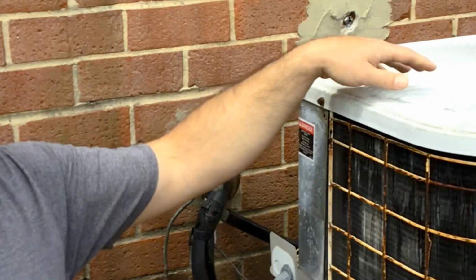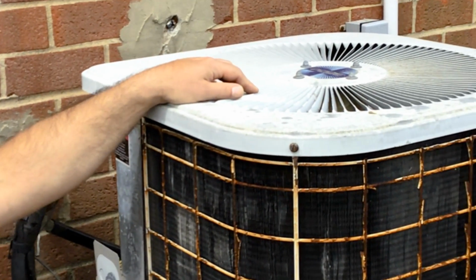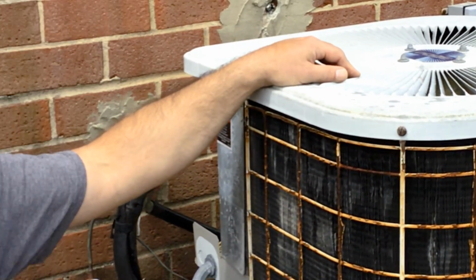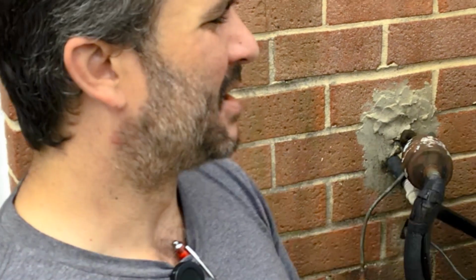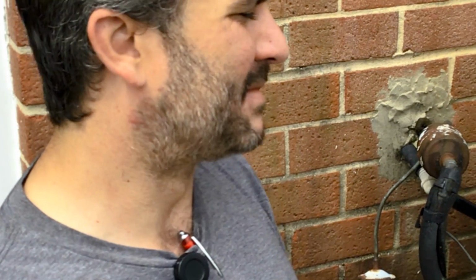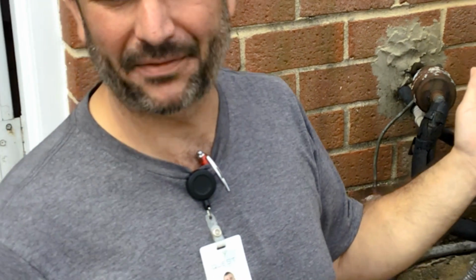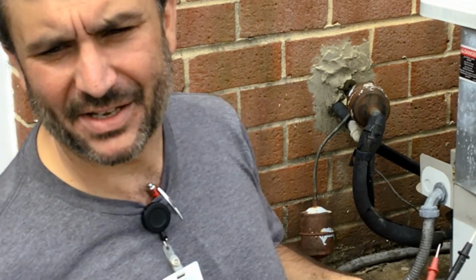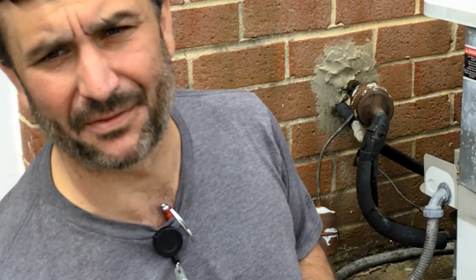So I recommend that anytime you're replacing an outdoor fan motor, you also purchase the fan hub and blade with it. These things sit outside and are full of rust, and I've seen it take longer to just get the old blade off than to actually replace the motor itself.